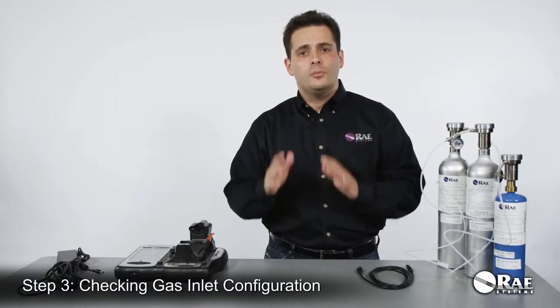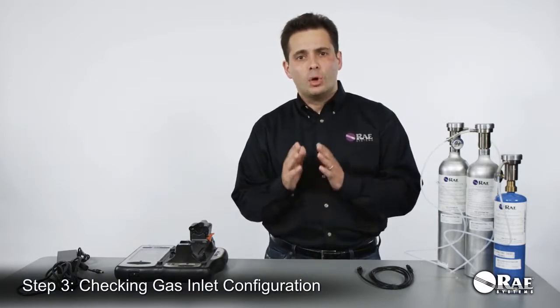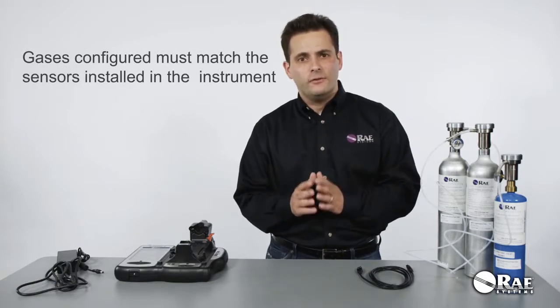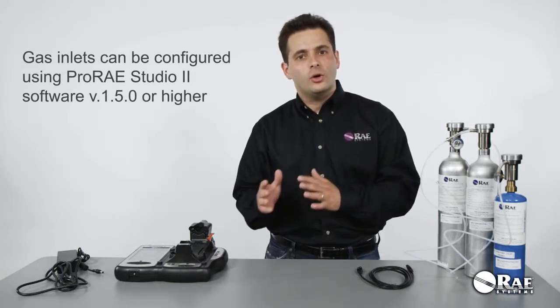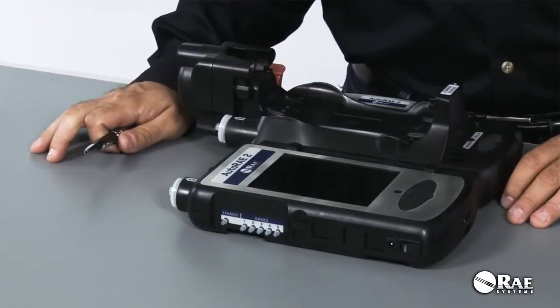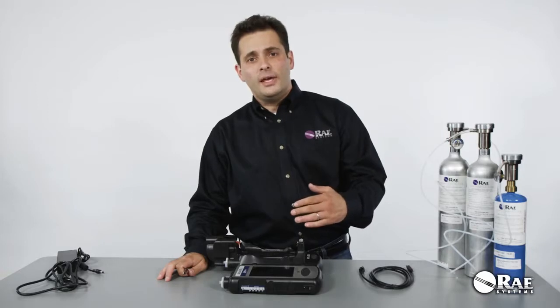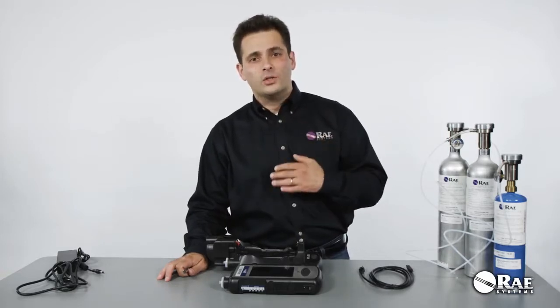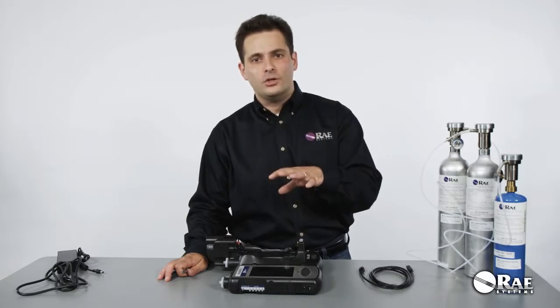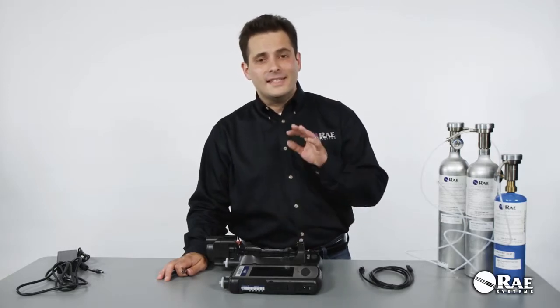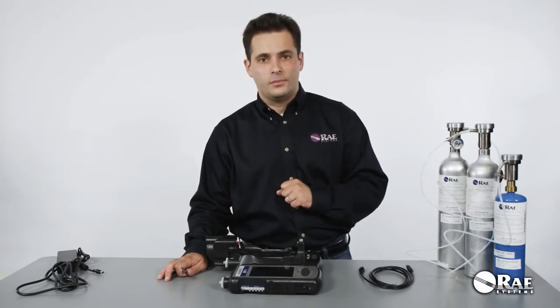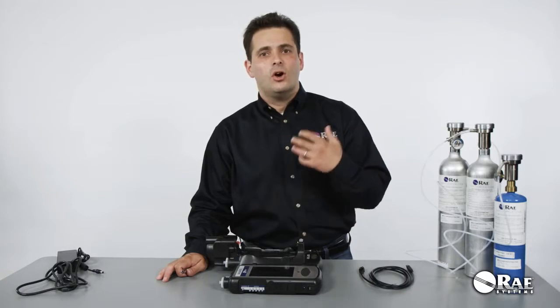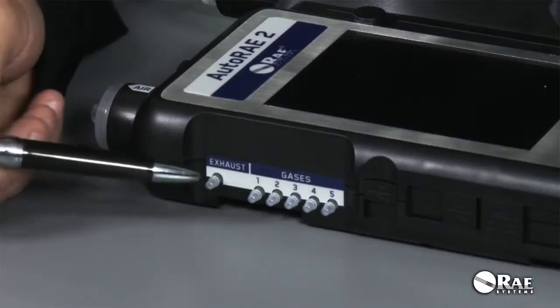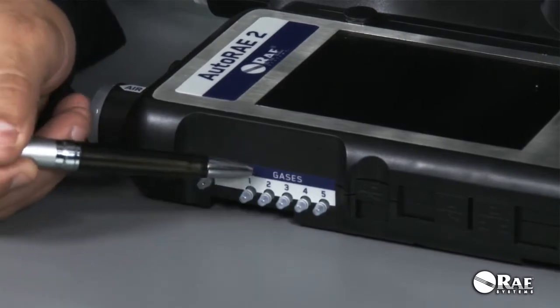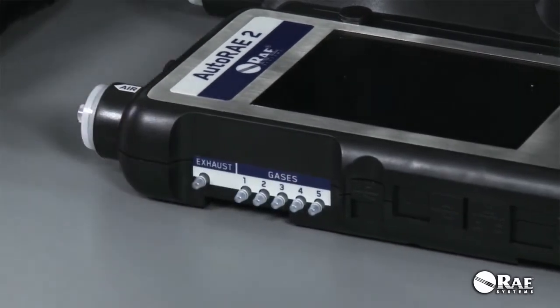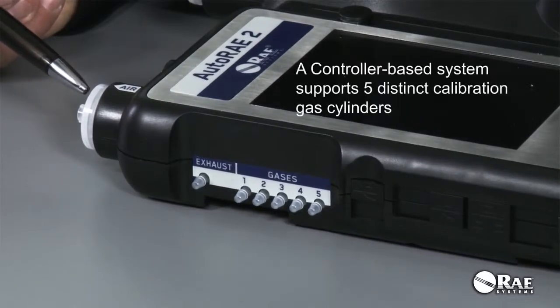The next step is to make sure that the gas inlets are properly configured to match the sensor configuration of the multi-array instruments that you are going to use with the AutoRAE 2. The benefit of a controller-based system is that in addition to being able to combine up to 10 individual cradles into one system that's centrally managed, you can also use up to 5 distinct gas cylinders with the system to accommodate various configurations of the multi-array instruments. So if you look at the left side of the controller, you will see 5 dedicated gas inlets, an exhaust port, and we always have a dedicated fresh air inlet.